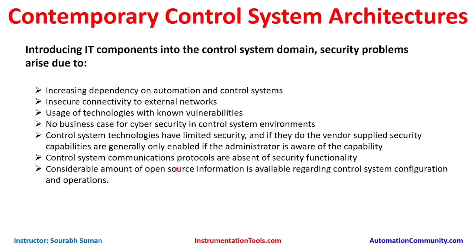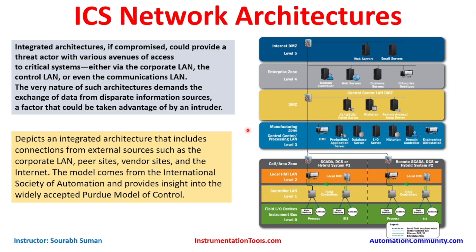Control system communication protocols are absent of security functionality. For example, RS-232 serial communications cannot implement cyber security, and OPC-DA is based on DCOM communications which already has too many vulnerabilities. Protocols that were designed without security cannot have certificates, SSH key exchange, or secure transport layer communications added to them. Additionally, a considerable amount of open-source information is available regarding control system configuration and operation. These are areas where we need to pay attention to mitigate existing gaps.